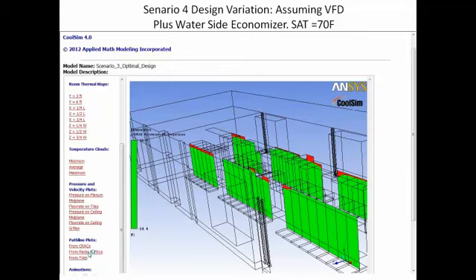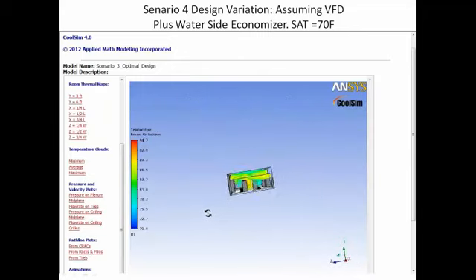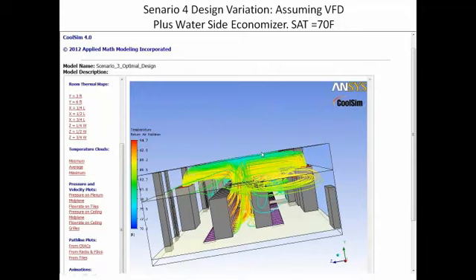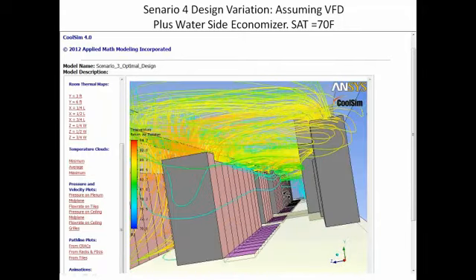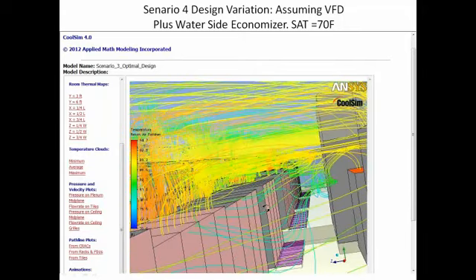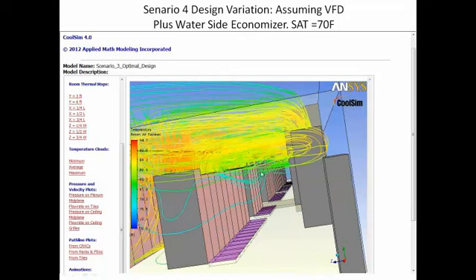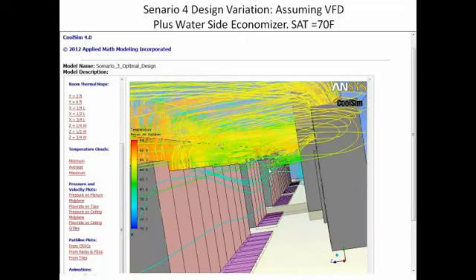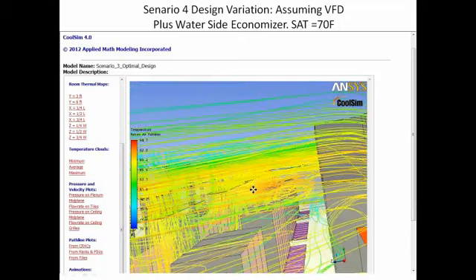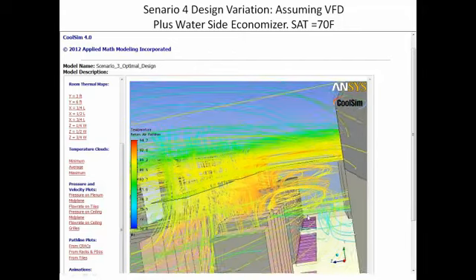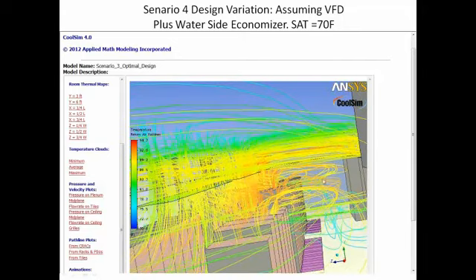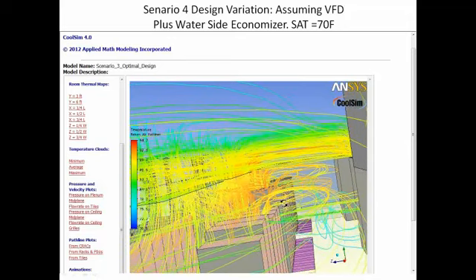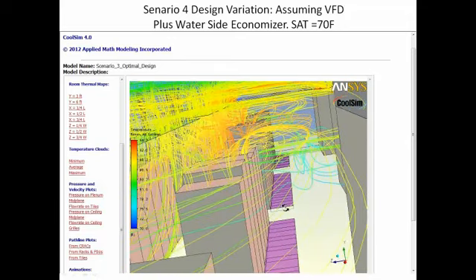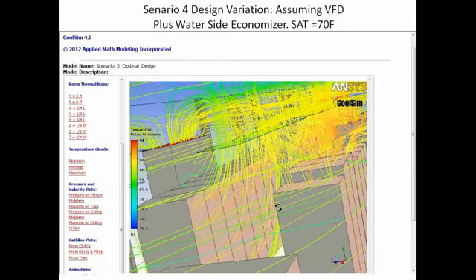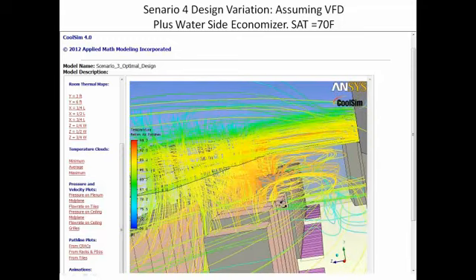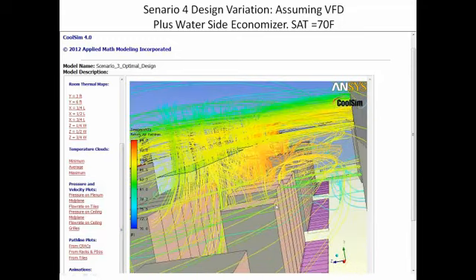Now, if we take a look at the path lines from the hot, and we zoom in tight, you can see again what's going on here. These are beginning to recirculate just a little bit, and you can see it right there. Front to tops beginning to breathe their own exhaust. If we go down here a little further into the section where it's kind of hot, you see they're starting to come around here and breathe their own intake, and that's where you run into it. But it only happens on the tall ones, the very tall ones, and it happens near the top, and it's a manageable situation.